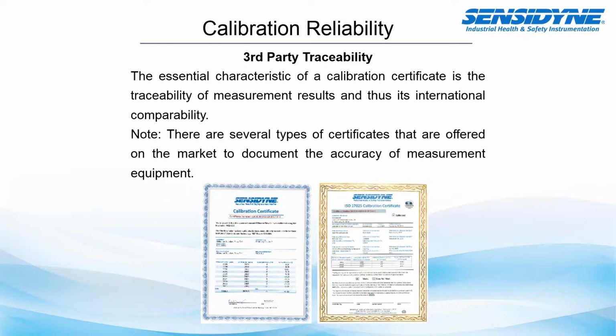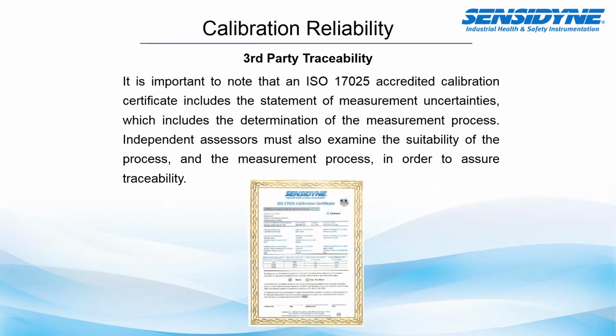The essential characteristics of a calibration certificate are both the traceability of measurement results and therefore its international comparability. It's important to note that there can be several types of certificates that are offered on the market to document the accuracy of measurement. Not all of these certificates are 17025 certified, although they all should be NIST traceable. The 17025 accredited certificates, again, will have additional data and factors of uncertainty. It is the statement of measurement uncertainties, which includes the determination of the measurement process. Independent assessors must also examine the suitability of the process and the measurement process in order to assure traceability. So again, this is where we say that a third-party audit needs to be completed for these ISO certified laboratories and manufacturers to ensure that the traceability and the process of calibration is being met.